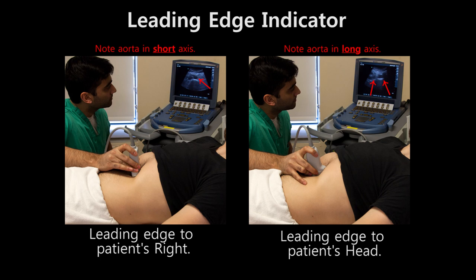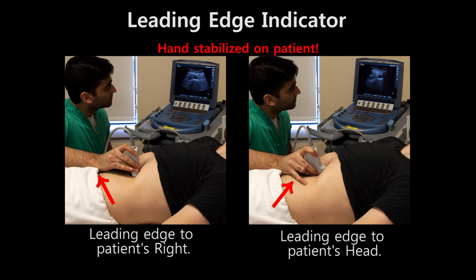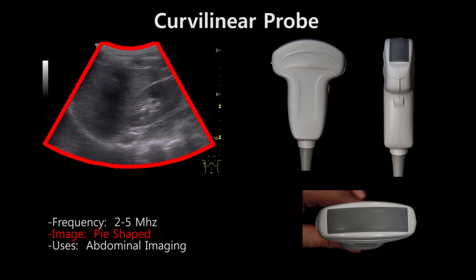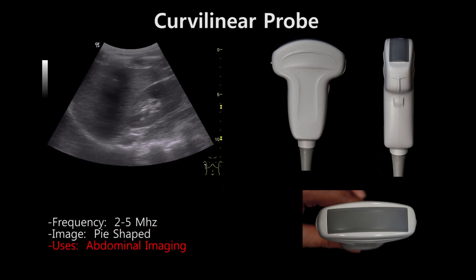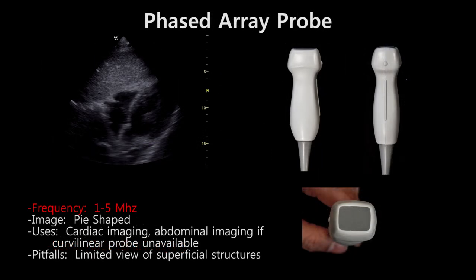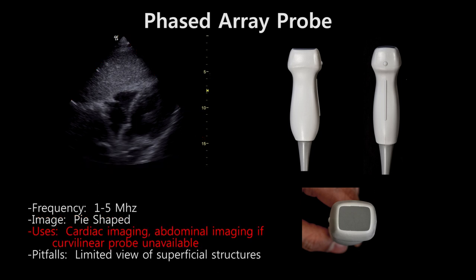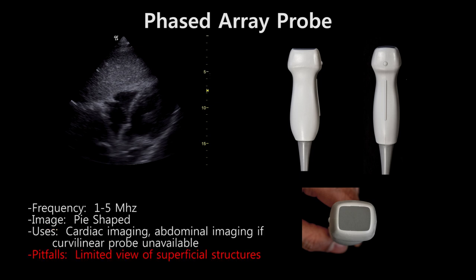Gel is used as a medium to transduce ultrasound waves. Use your hand to stabilize the probe on the patient. The curvilinear probe transmits between 2 to 5 megahertz frequency. It is characterized by low resolution but high penetrance. It gives a pie-shaped image and is typically used for abdominal imaging. The phased array probe transmits at 1 to 5 megahertz frequency, with moderate resolution and moderate penetrance. It gives a pie-shaped image with a narrower point than the curvilinear probe, and is typically used for echocardiograms and imaging between rib spaces given its small footprint. When a curvilinear probe is not available, the phased array can be used for abdominal applications such as the FAST scan, though its smaller footprint gives a less complete view of structures close to the probe.